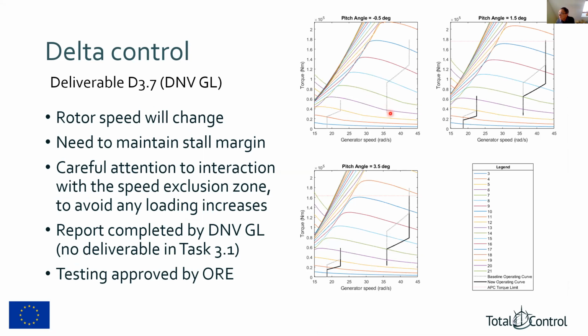So this is generator speed and torque on this graph, and this is the normal trajectory that we would have here with a big exclusion zone. Then for the different delta settings, we increase the pitch angle, we change these characteristics, and we had to change the parameters which control the crossing of the speed exclusion zone, in order to make sure we don't cross that zone too often or at the wrong times, and we cross it at a suitable speed and so on. So that's all ready and done.